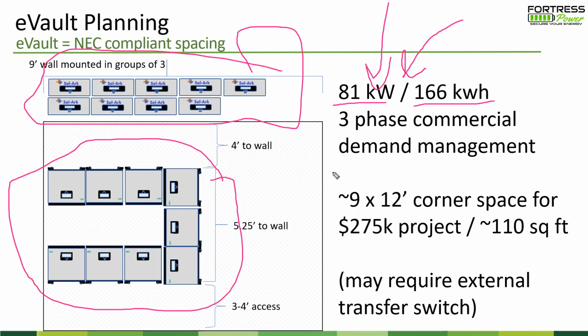This might be a very large commercial facility with a 500 kW load, but its peak load has an 80 kilowatt hysteresis at the top where it's jumping up and down. You're using demand management to shave off the very top of that peak load.